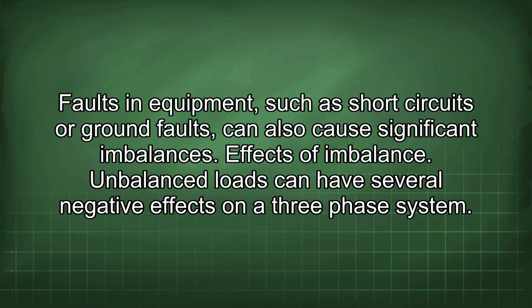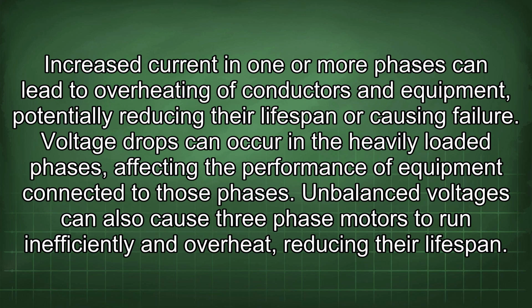Effects of imbalance. Unbalanced loads can have several negative effects on a three-phase system. Increased current in one or more phases can lead to overheating of conductors and equipment, potentially reducing their lifespan or causing failure.